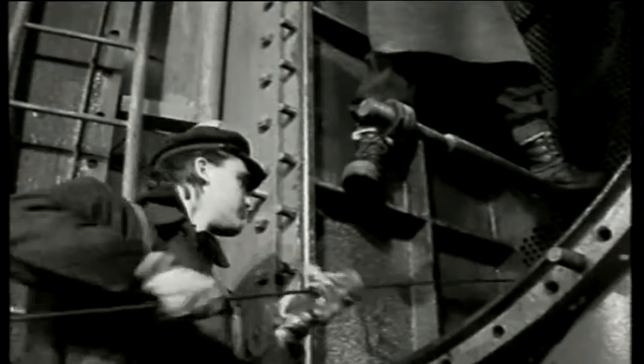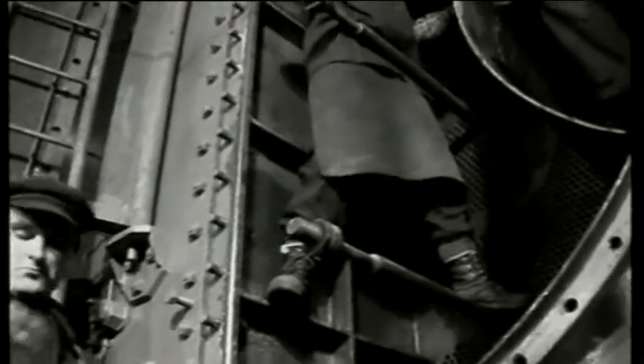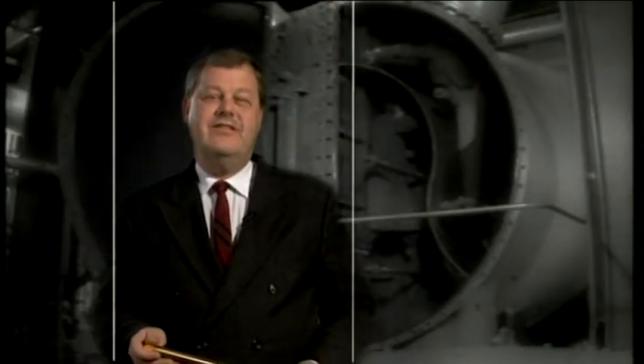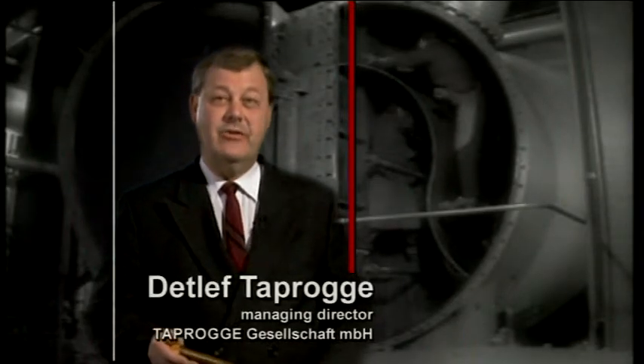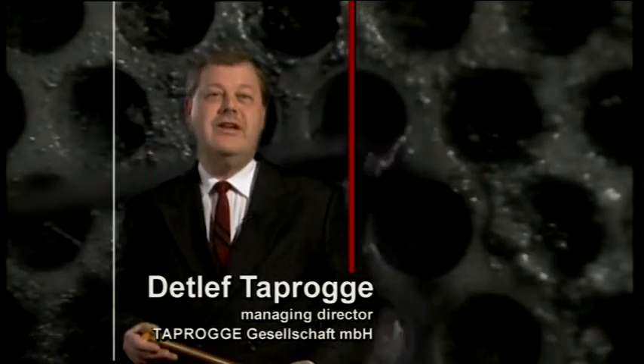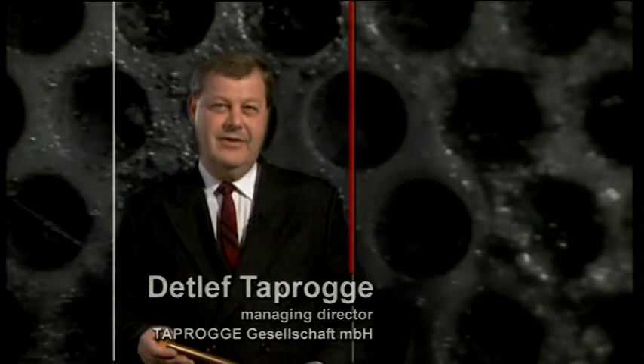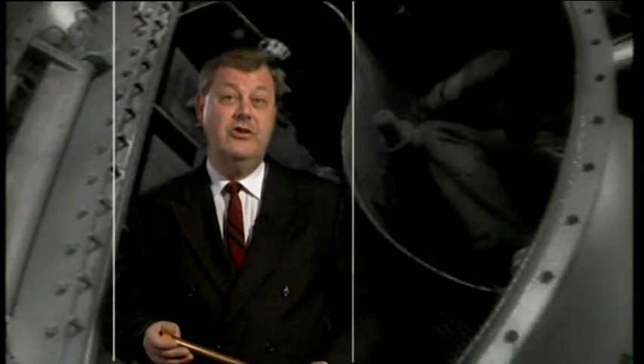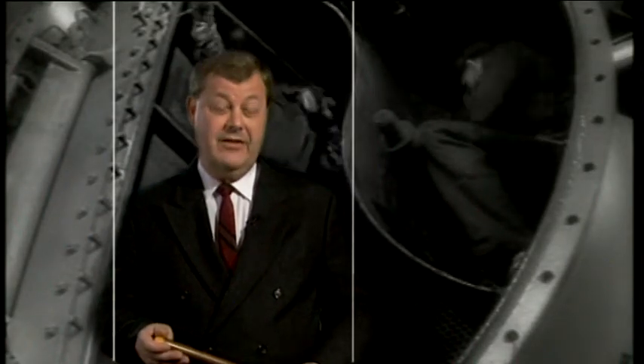Taprogge, entrepreneur and managing director of Taprogge GmbH, has witnessed this development. Until the early 50s, power plants still had to derate or shut down a unit in order to manually clean condenser tubes. This certainly meant lost power sales due to non-availability and, even worse, efficiency losses due to the ongoing and continuous fouling of condenser tubes during operation.